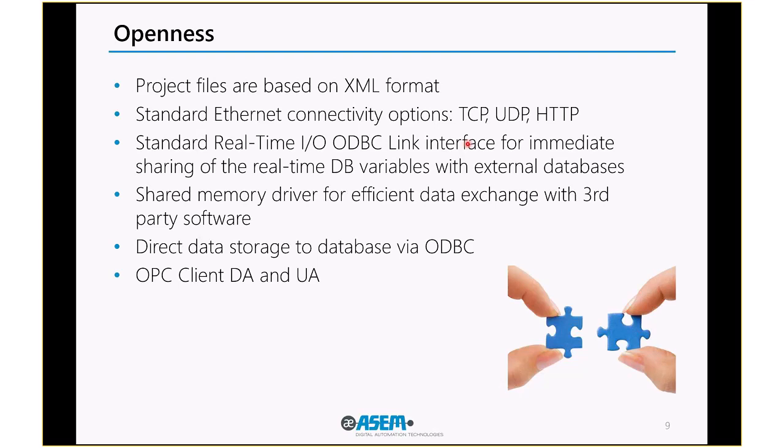We are supporting standard Ethernet connectivity, so TCP, UDP, HTTP. We have standard support for ODBC, so we can connect to external databases. This is true only for the Windows runtime. From the Windows CE devices, we cannot connect to external databases.